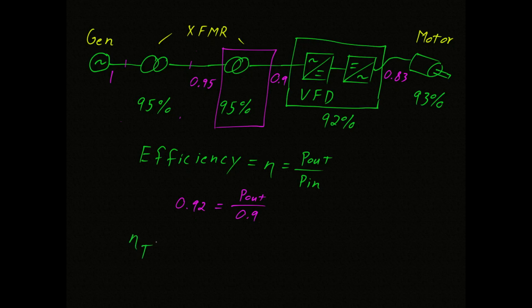We could go one step further, but I think you see the pattern. The total system efficiency is equal to the product of the individual efficiencies. So in this case, it's 0.95 times 0.95. That takes care of both transformers. The variable frequency drive is 0.92, and the motor is 0.93, which gives us a total system efficiency of 77%.